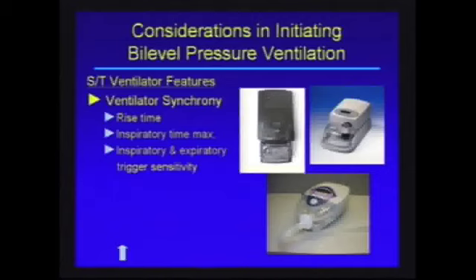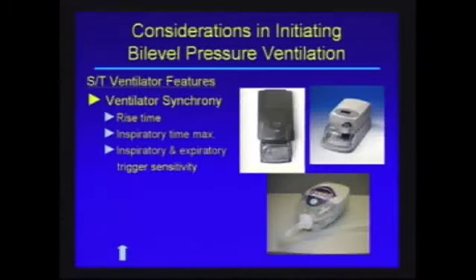The inspiratory time maximum allows the person who's adjusting this system for you to set it up according to what you feel is adequate time to breathe in. This is important not only in the backup mode, but also in your spontaneous mode. On some ventilators, you have inspiratory and expiratory trigger sensitivities, and these can be adjusted, again, in order to make the system actually in sync with your breathing.